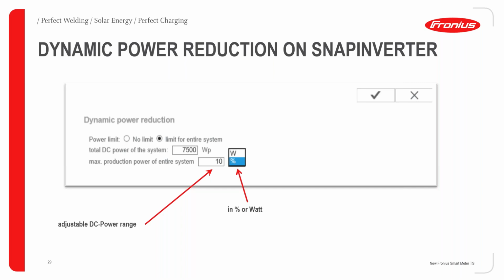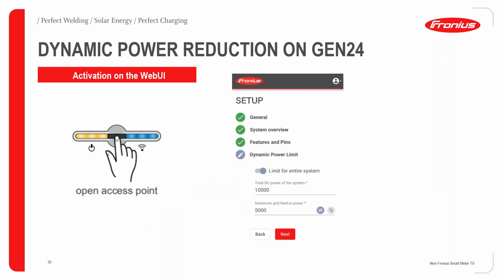Then you have to enter the watt power here. Or in case you have this new Gen 24, and you want to limit your output power or the feed-in power into the system, then you will have an option directly under the setup menu. You have to access the interface page the same way. Whenever you want to do some setting change in the data manager or the pilot, you have to access the interface page. This is not possible remotely unless the customer opens a port forwarding in his router. So if he opens a port in his router, then he will allow you to access his system remotely. Then you can do this. Otherwise, you have to be on site. You have to be in the same network as the inverter to access this interface page.